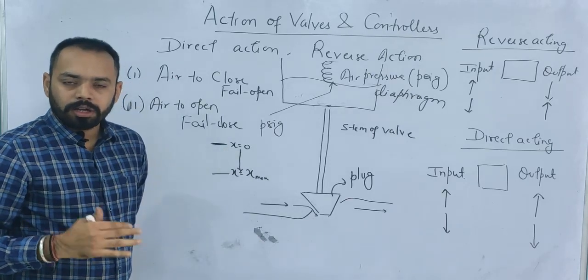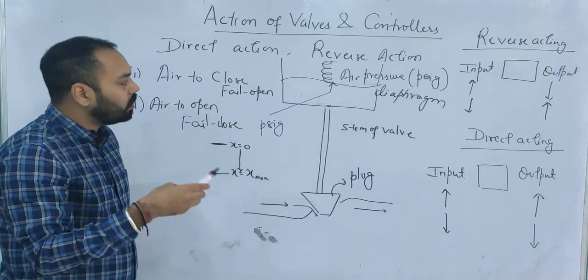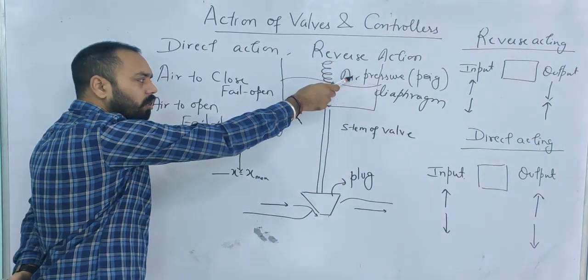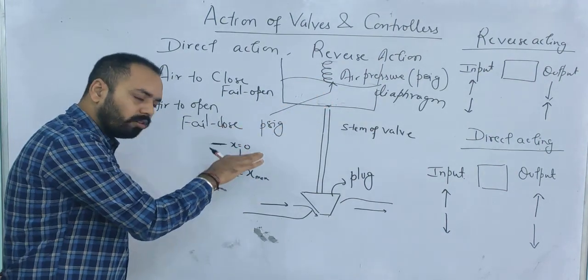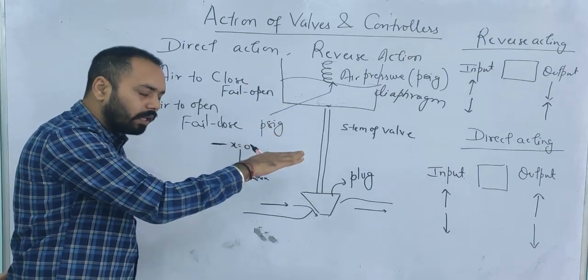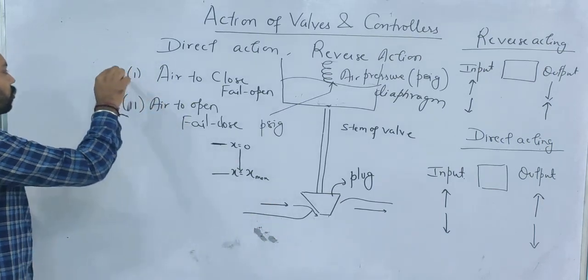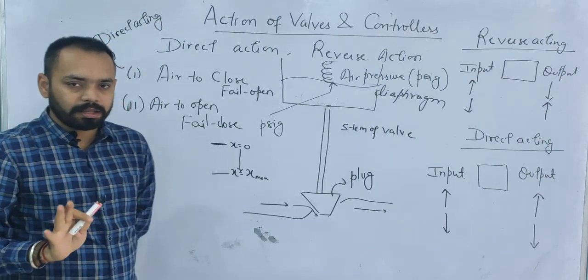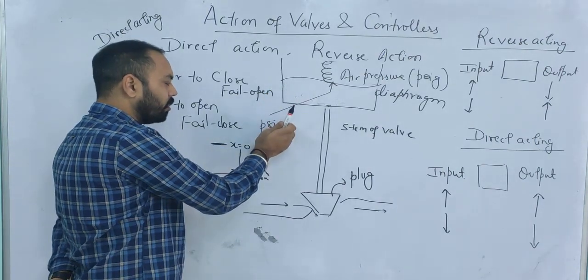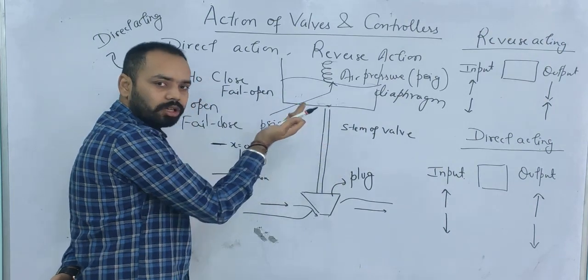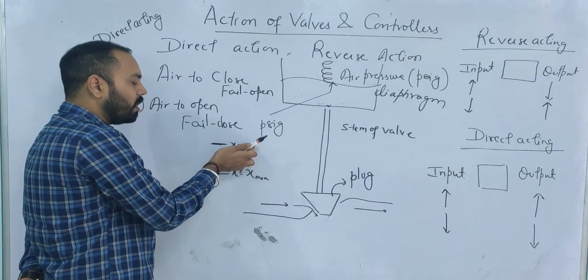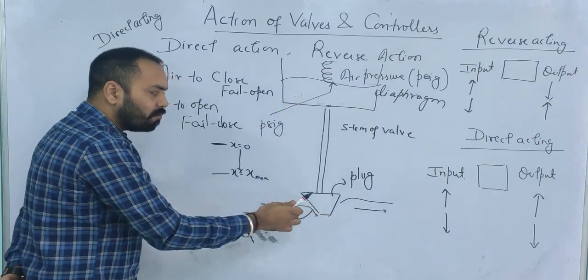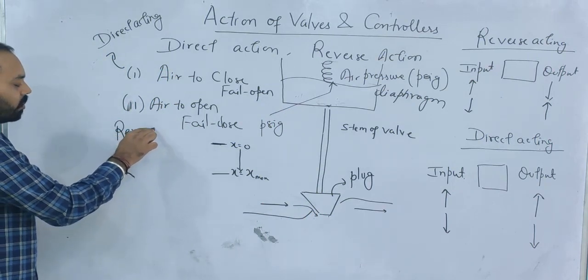Now apply this to the air-to-close valve: the spring is below and the signal comes from the top. As air pressure increases, the stem moves downward — in the positive direction. So air pressure increases and stem movement increases. Therefore, the air-to-close valve is called a direct acting valve. Similarly, for air-to-open, as air pressure increases, the stem moves from x-max to x-zero — the negative direction — so stem movement decreases. Therefore, the air-to-open valve is called a reverse acting valve.